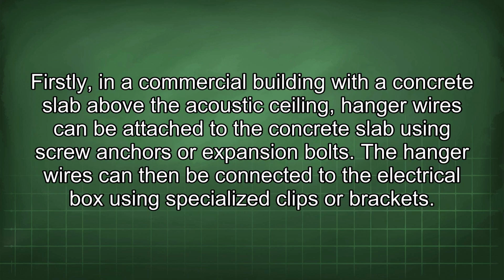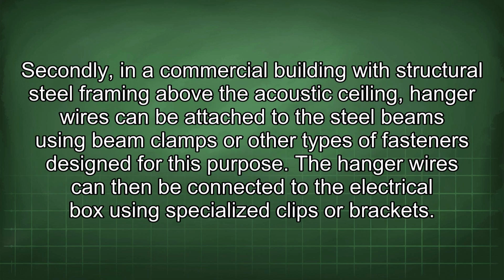Firstly, in a commercial building with a concrete slab above the acoustic ceiling, hanger wires can be attached to the concrete slab using screw anchors or expansion bolts. The hanger wires can then be connected to the electrical box using specialized clips or brackets. Secondly, in a commercial building with structural steel framing above the acoustic ceiling, hanger wires can be attached to the steel beams using beam clamps or other types of fasteners designed for this purpose. The hanger wires can then be connected to the electrical box using specialized clips or brackets.